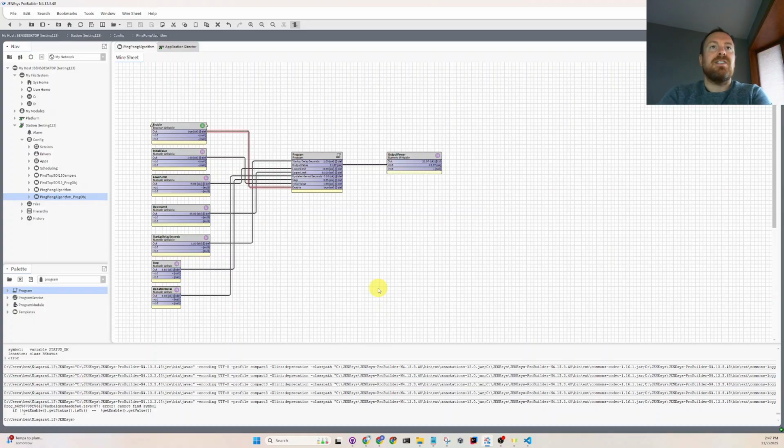So I know this isn't anything very fancy, but it is the core concepts of Guideline 36. So like if we were, which we'll get to eventually, resetting the air handling unit duct static pressure set point based on trim and respond counting logic between a minimum and maximum values that the duct static would go, we need to set an initial value, a step size, if the algorithm is enabled, and also how fast we're updating.